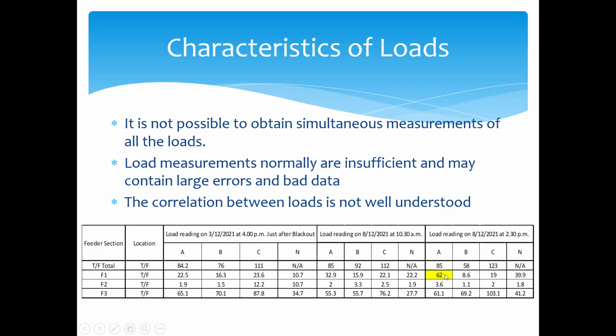We don't know. There may be an instant load. For example, one time when I took the load measurement to load balance the feeder, all of a sudden the value went high in one place. When I went along the distribution line, I found a twin mill, but it's operating in single phase mode. So once they switch on these machines, the current increases only in one feeder. So this may be due to some kind of load like that. Still, we don't know whether this one is the accurate one or not.